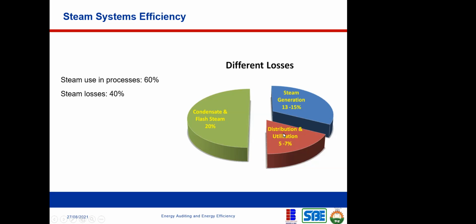Then you have distribution and utilization. Some of the processes that you're using the heat to accomplish, some of them are inefficient systems. Like maybe your heat exchanger might not be operating properly. Maybe you have some kind of debris or some kind of thing covering the heat exchanging medium, so that it is not highly effective. So all of these are what causes this 40% losses.